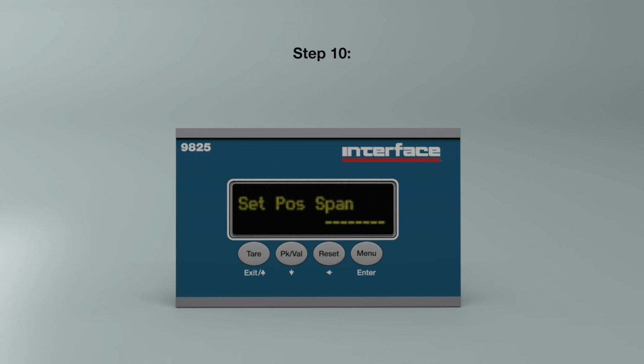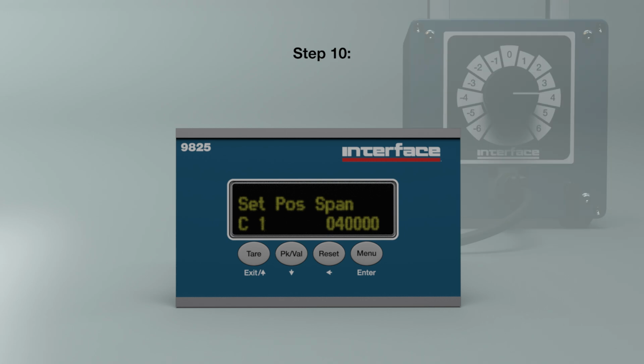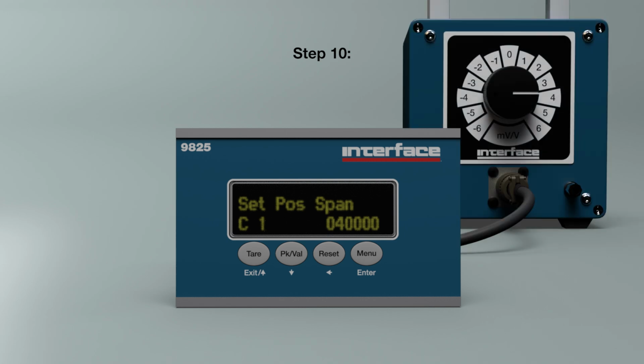Step 10. Once the 9825 has finished recording the fixture value, C1 will be displayed. For this example, we will use a load simulator to input 4 millivolt per volt. Make sure that the load simulator is set to output 4 millivolt per volt, then use the reset key to scroll through the digits. Use the tare and peak and valley keys to set the C1 value to 40,000. With the load simulator set to 4 millivolt per volt and C1 set to 40,000, press the menu key to set the C1 value. A dashed line will migrate across the display as the 9825 records the input.